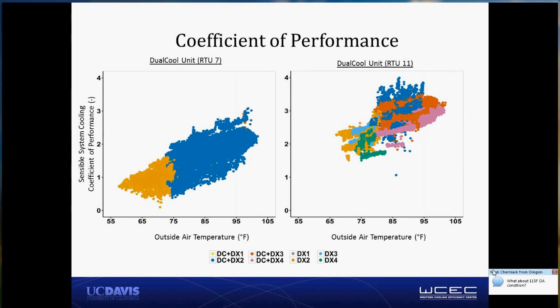We see a significant coefficient of performance increase for the dual cool. This shows also, well, this doesn't show comparison to baseline. This shows coefficient of performance for two different dual cool units on the rooftop. One of the things to note is that there are significant differences between rooftop units. In fact, one of the big conclusions from this study is that these type of retrofits really should be installed in cooperation with a quality maintenance or retro-commissioning program.